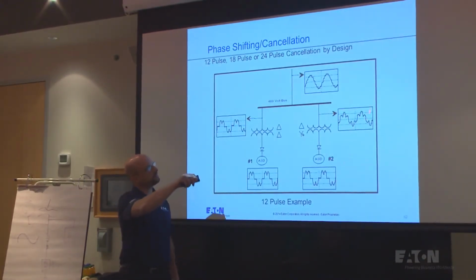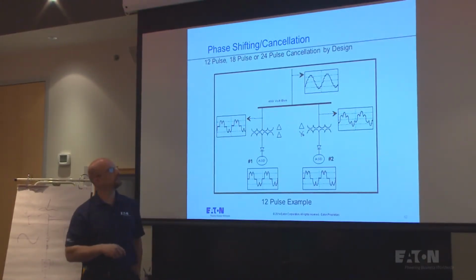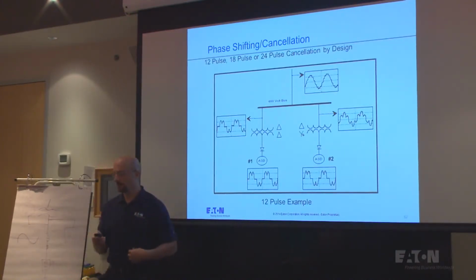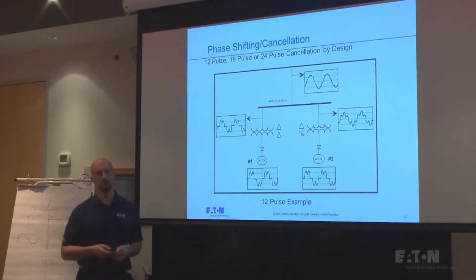This one gets shifted by 30 degrees at 60 hertz, but it turns out your fifth and seventh are shifted by 180 degrees from each other, and you end up with what's called a 12-pulse system. Your fifth and seventh cancel each other from here and here. I'll show you a video of that later, but it really works well. So it's a really good way to do that.